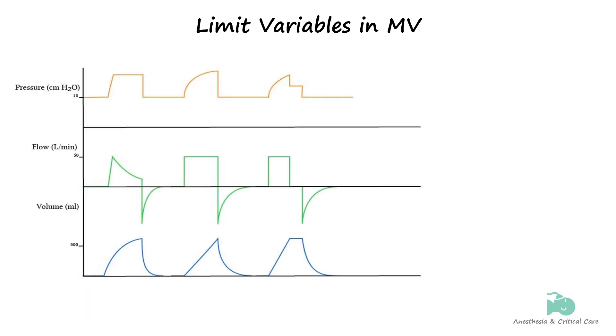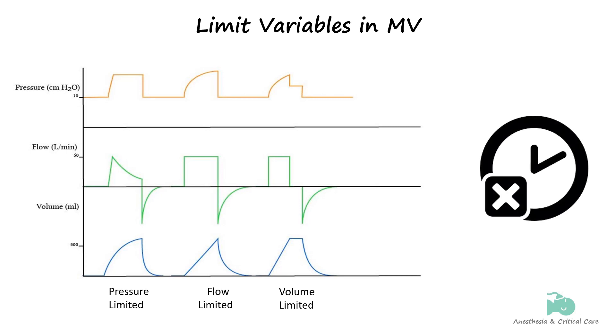The three main limit variables in routine use are pressure, flow, and volume limits. Time, of course, cannot be a limit variable, because with a time-limited breath, the breath would have to end, and that would be cycling.